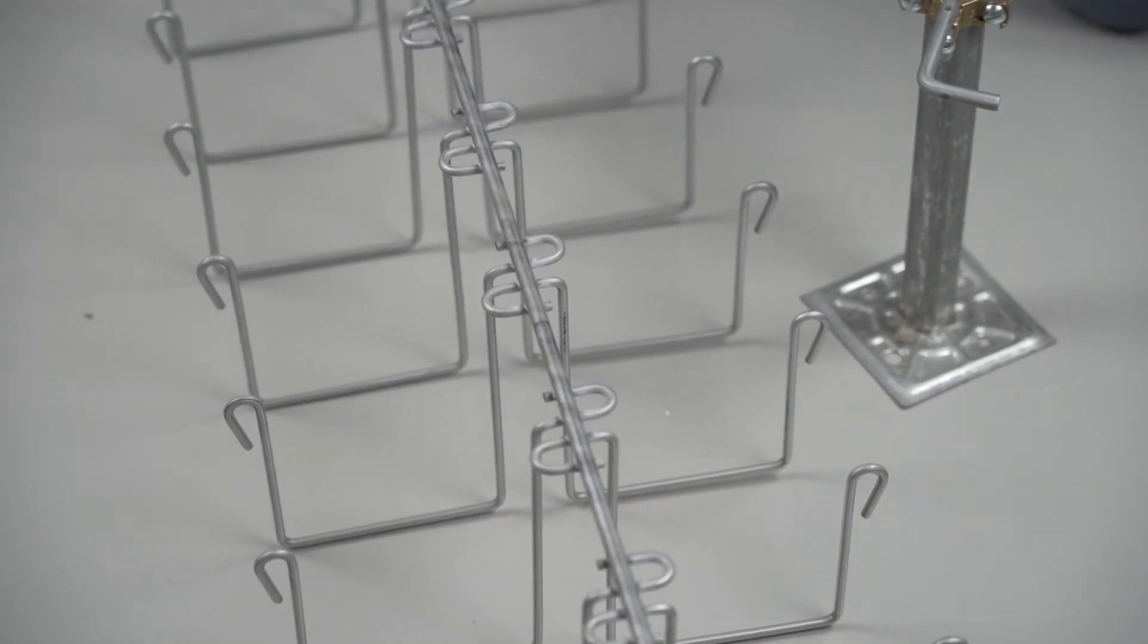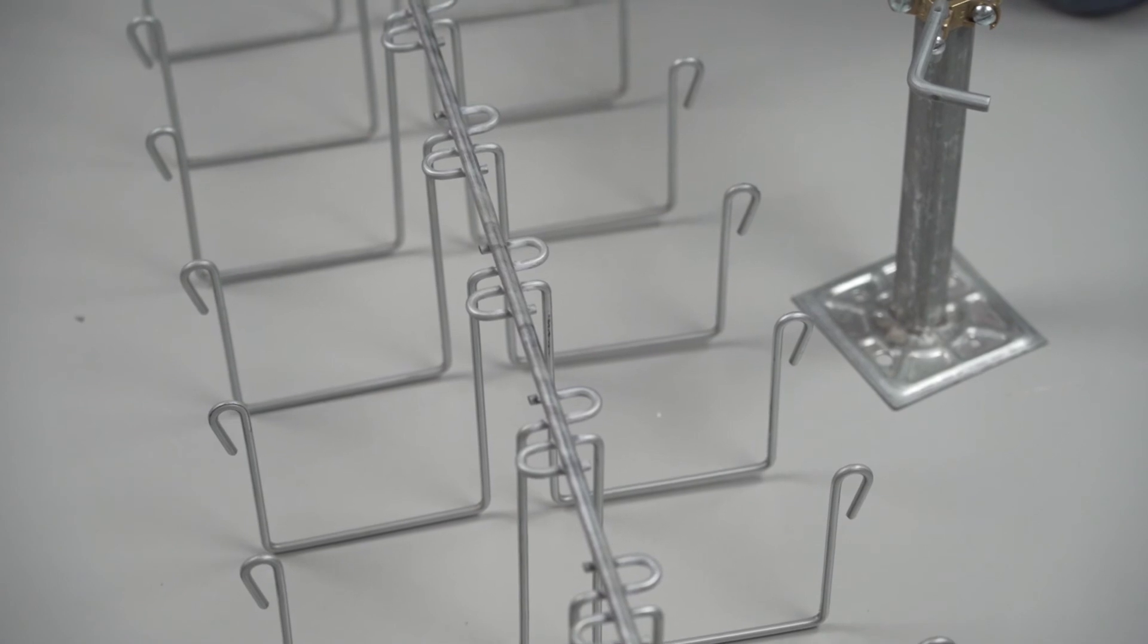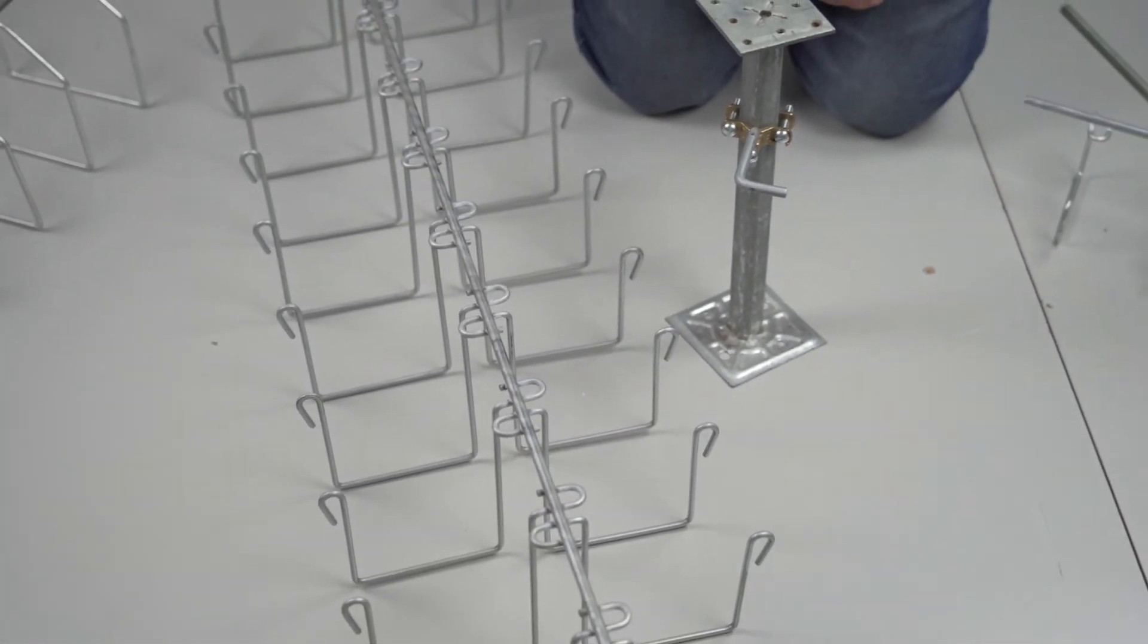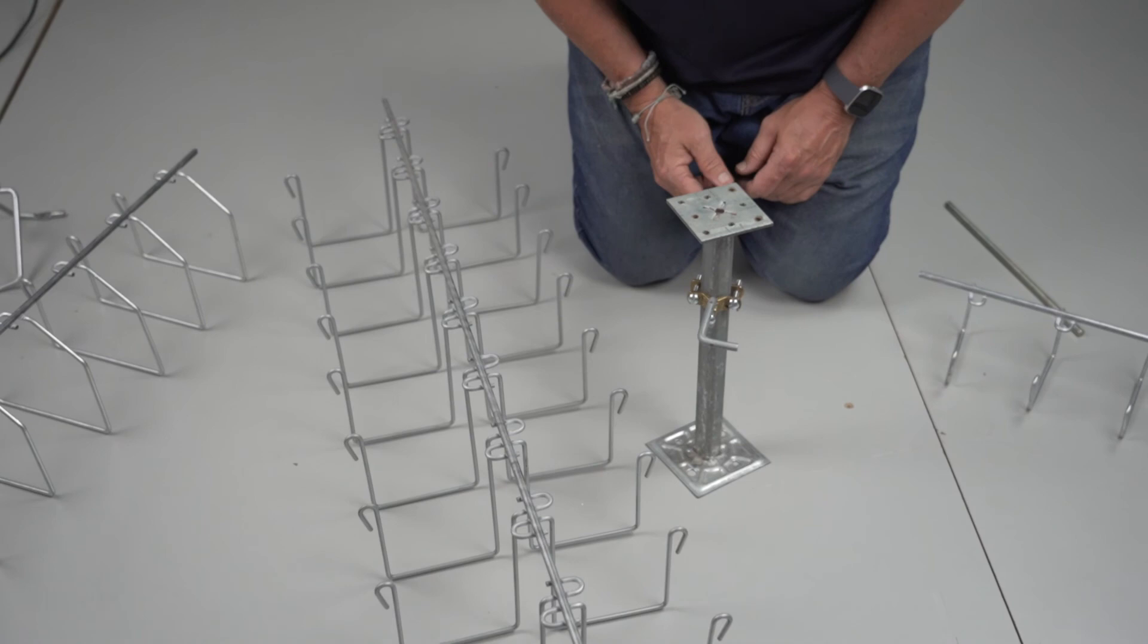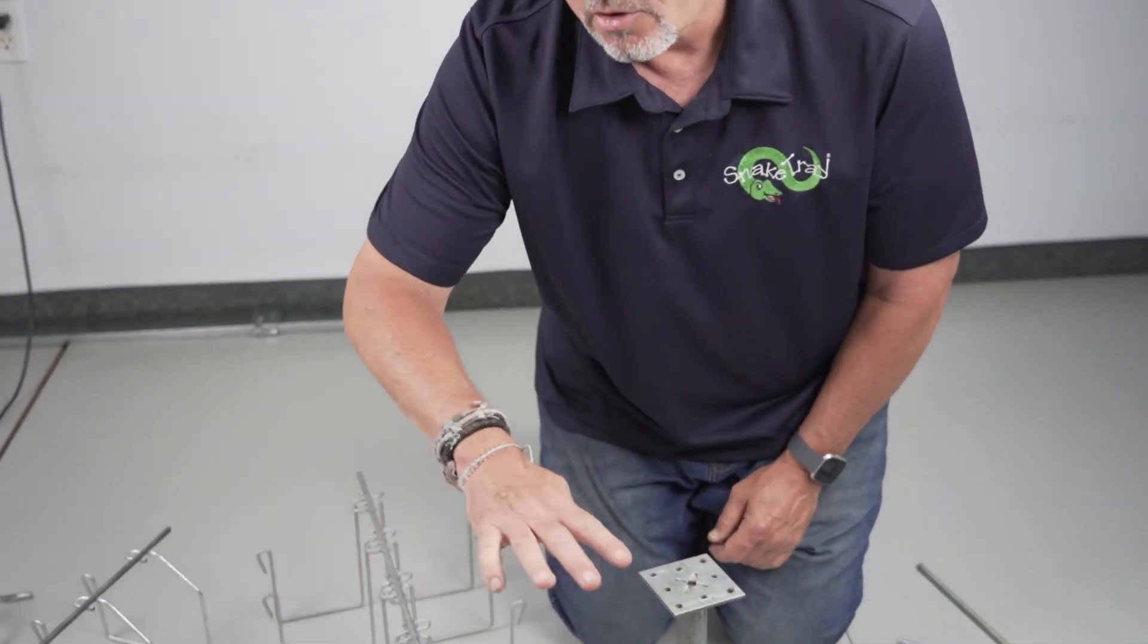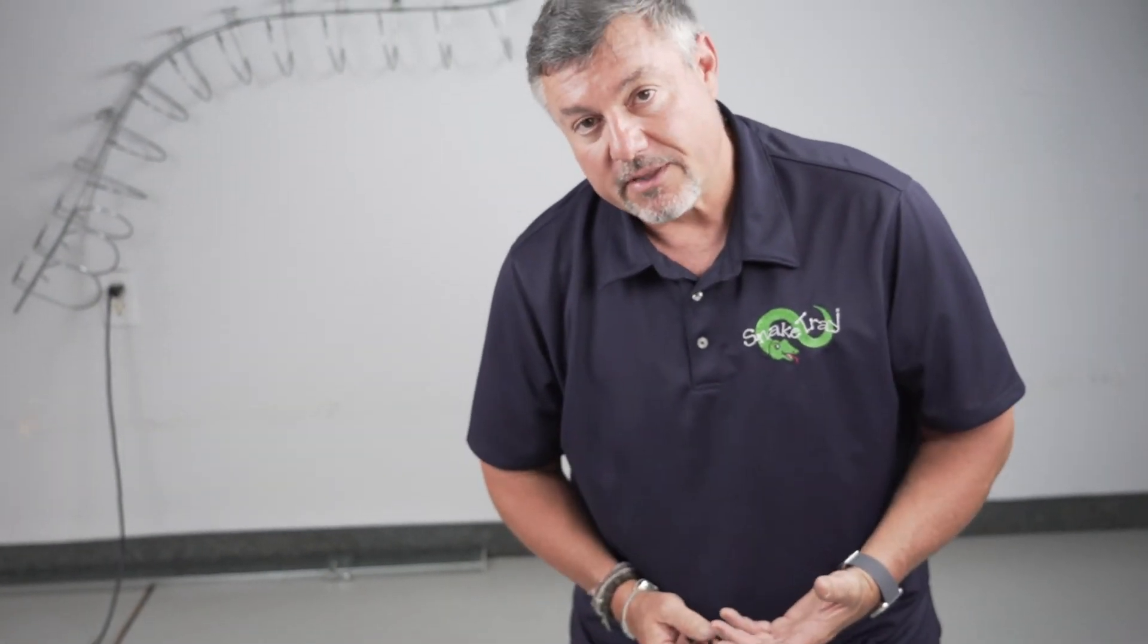So anytime that you're thinking about installing cables into a small office space or say into a renovated building construction, the 201 series trays are very good for those applications because they're hand bendable. One of the things that we've noticed is that with an older building, if we're going to renovate those buildings, there's really never been a pathway that's designed into the space. So being able to utilize a hand bendable system such as Snake Tray makes installation go much, much faster.